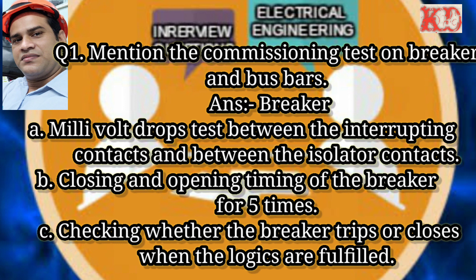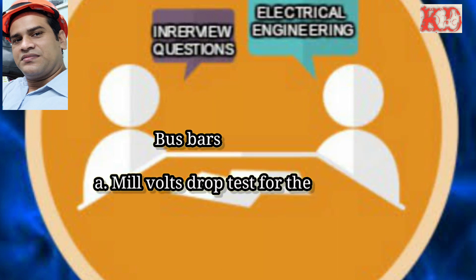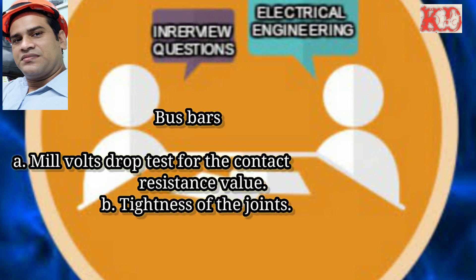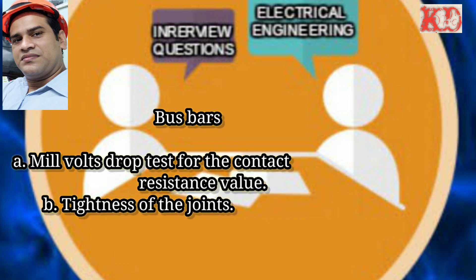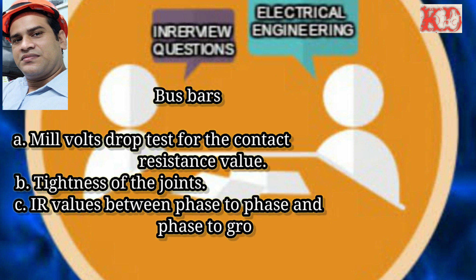For bus bar commissioning test, keep in mind: first, millivolt drop test for the contact resistance value; second, tightness of the joints; third, higher insulation resistance values between phase-phase, and phase-to-ground.